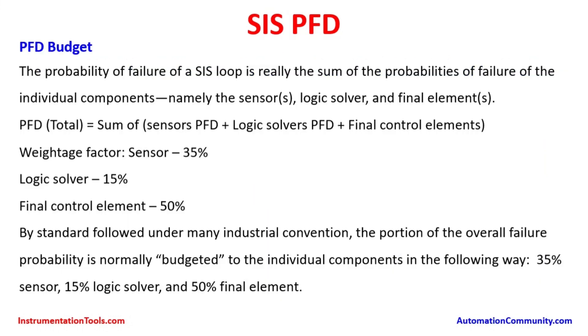PFD budget — now we will discuss the PFD budget and how it has to be taken into account. The probability of failure for a SIF loop is really the sum of the probabilities of failure of the individual components, namely the sensors, logic solver, and final elements. So the PFD total equals the sum of sensor PFD, plus logic solver PFD, plus final control elements PFD.